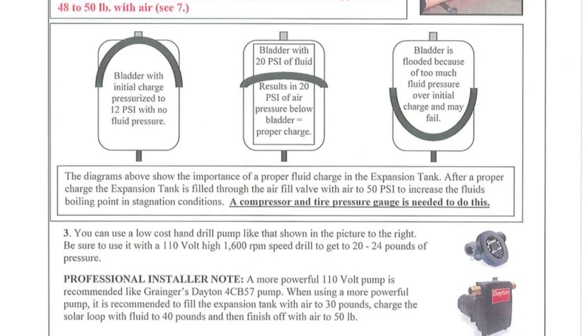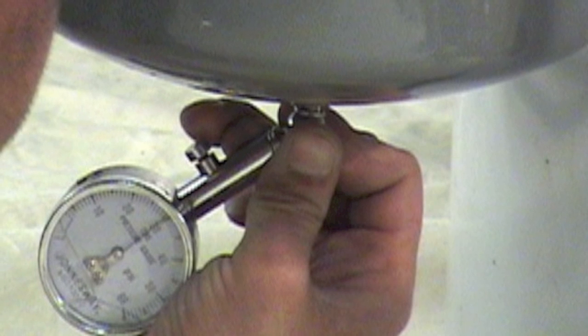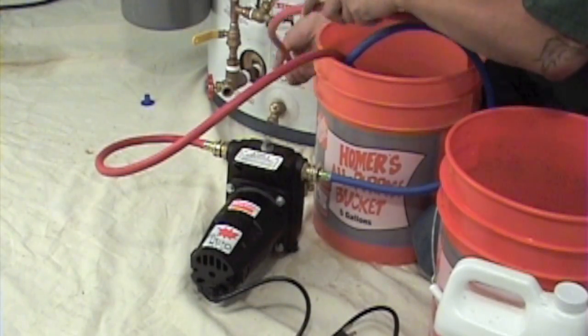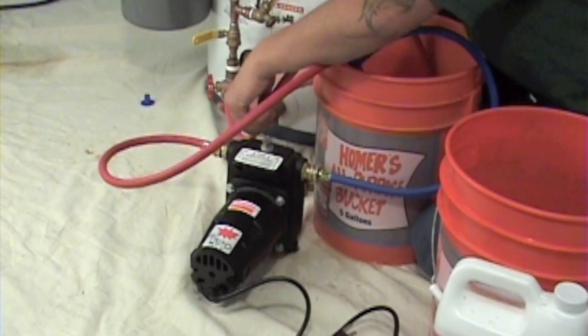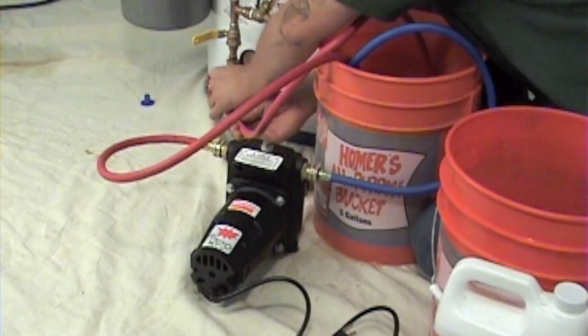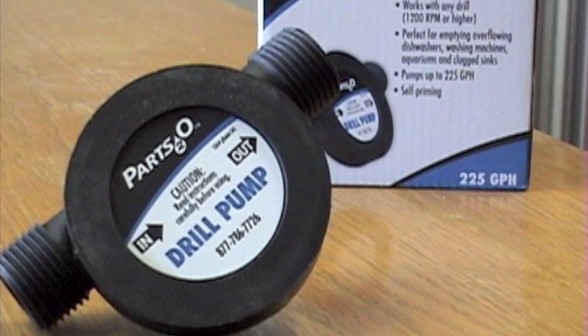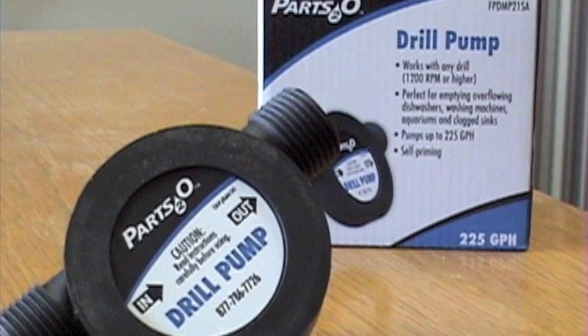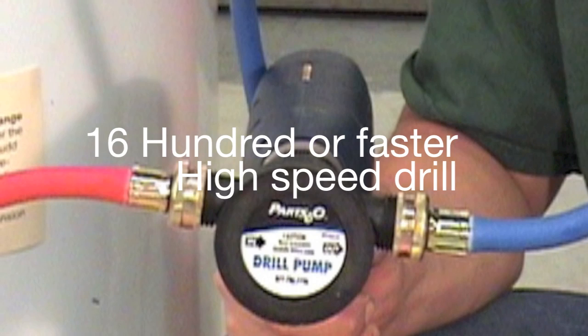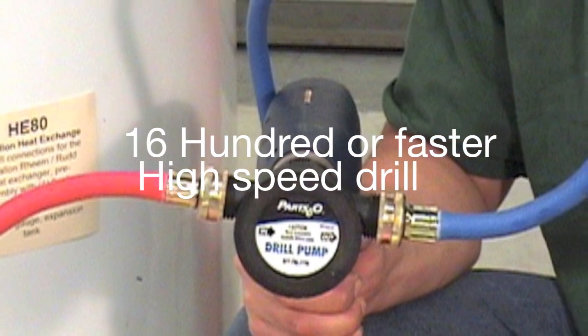It is vital to check the air pressure in the expansion tank before charging the solar loop. This is done by using a standard pressure gauge at the air valve on the bottom of the tank as shown. If you're using a high pressure professional pump like the Grainger's Dayton 4CB57 pump shown in this video, pressurize the expansion tank to 30 pounds. If you're using a low pressure pump such as a drill pump, be sure the air pressure is about 12 pounds, because a drill pump can only build up to 20 to 22 pounds of pressure on the fluid side when using a 1600 RPM or faster 110-volt high speed drill.